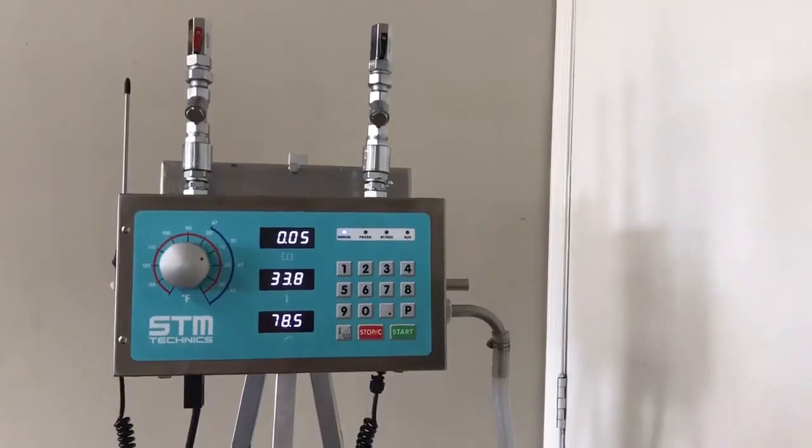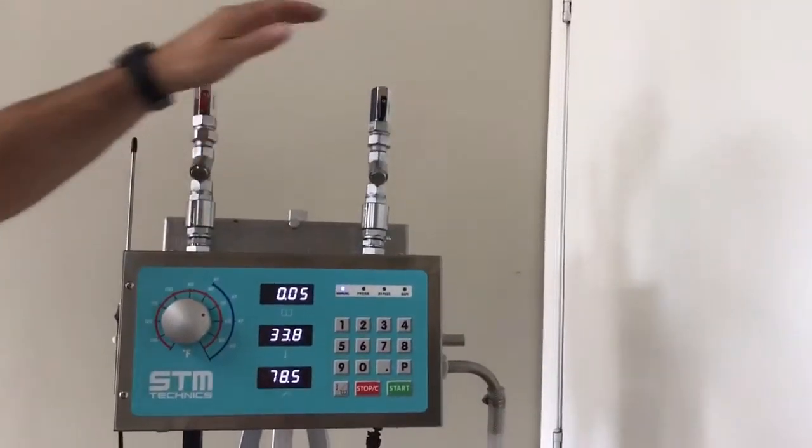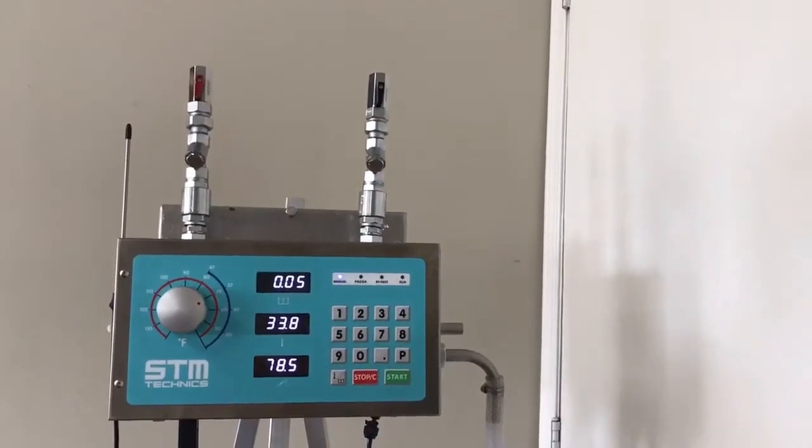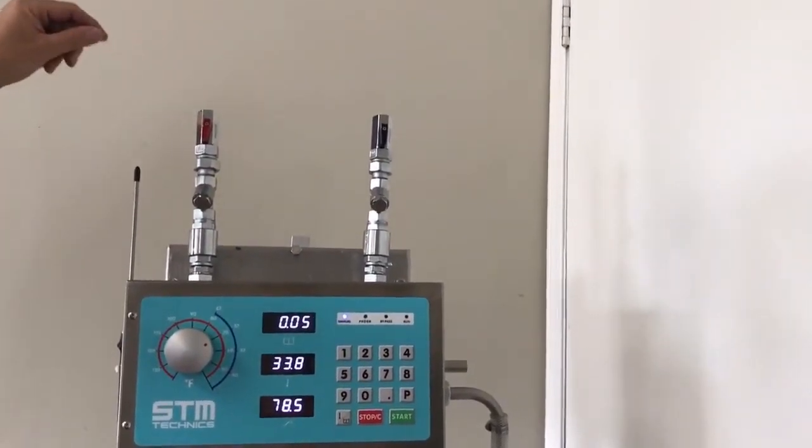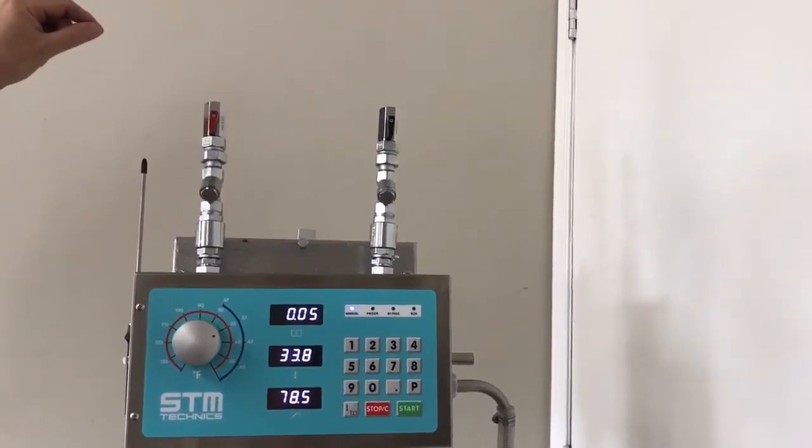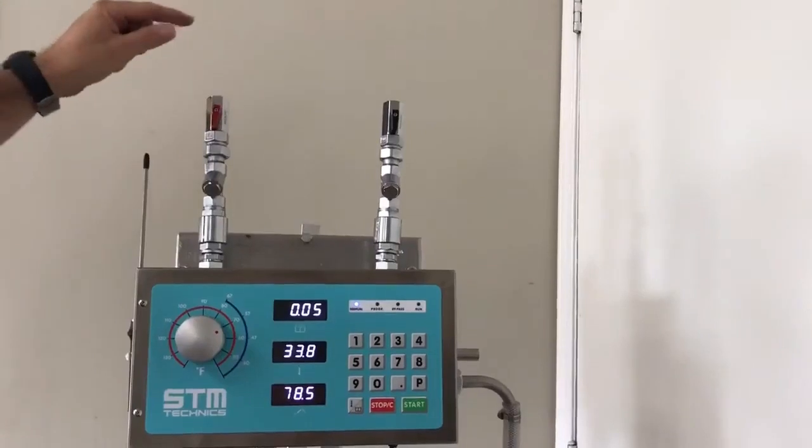The unit needs between 45 to 50 psi for both the hot and cold line. In addition, the supply line should be fitted with a hammer arrestor or shock arrestor and a PRV valve to reduce the pressure to 45 to 50 psi.